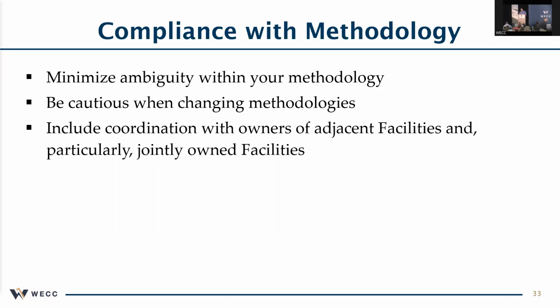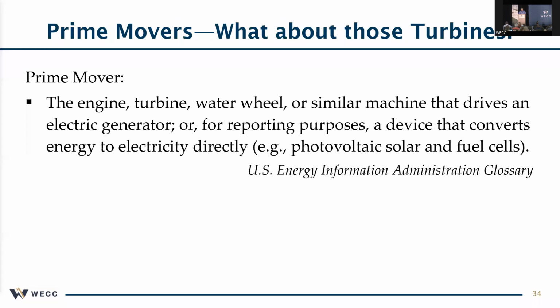The other piece, when you have other owners, coordinate with those other owners so that both people are coming up with the same value. It used to be a requirement that, in the case of any disagreement, always operate to the most limiting element. If facility owners did this, you'd probably never run into that situation. Everybody would be agreeing on those facilities. So that's my spiel on facilities and joint ownership.